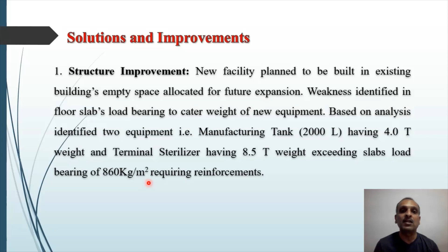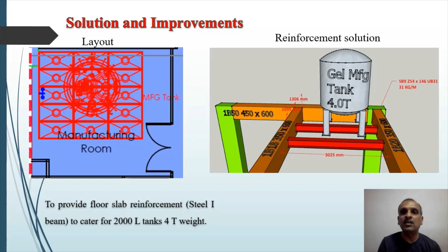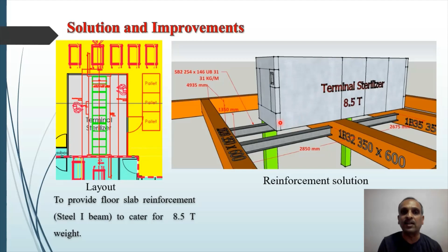So a slab steel I-beam reinforcement of appropriate size is proposed, as can be seen in this diagram, to cater for the 4 ton weight of the gel manufacturing tank. Similarly, an appropriate size steel I-beam reinforcement for the slab is proposed to cater for the 8.5 ton load of the terminal sterilizer, which can be seen in this diagram.